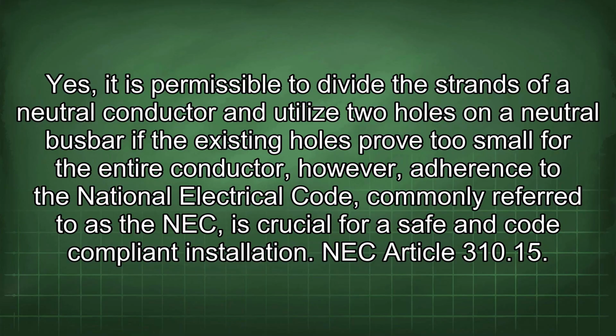Yes, it is permissible to divide the strands of a neutral conductor and utilize two holes on a neutral busbar if the existing holes prove too small for the entire conductor. However, adherence to the National Electrical Code, commonly referred to as the NEC, is crucial for safe and code-compliant installation.